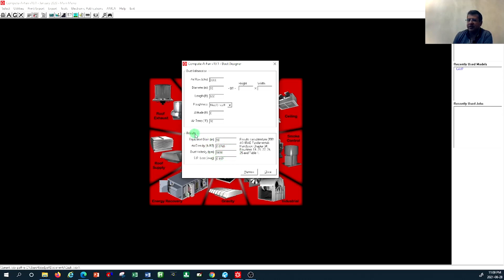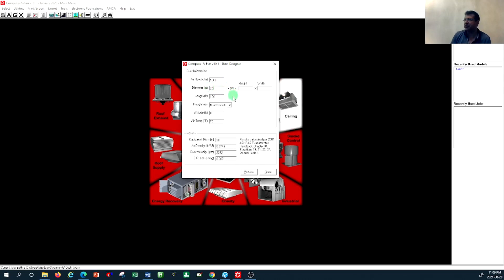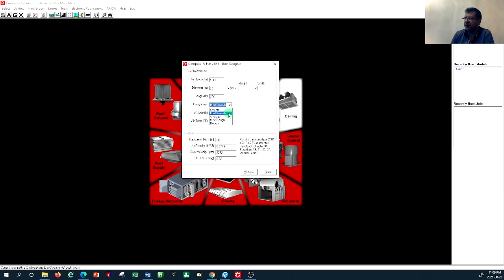The results are calculated based on the parameters you provided. For example, if I'm sizing an exhaust fan that delivers 5000 CFM and I select a 20-inch round duct with a length of 300 feet from the exhaust air outlet to where I exhaust out of the building, I'll keep the duct roughness as medium smooth. Remember you have different options depending on the roughness of the interior duct work surface. These roughness categories are referenced to ASHRAE standards — specifically the ASHRAE duct roughness factor from ASHRAE Fundamentals.